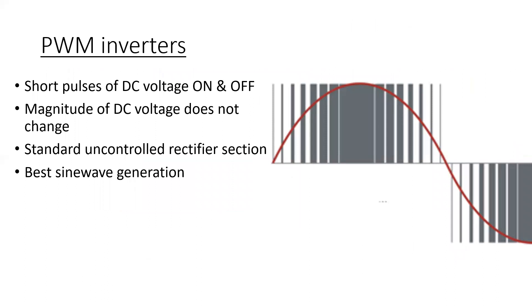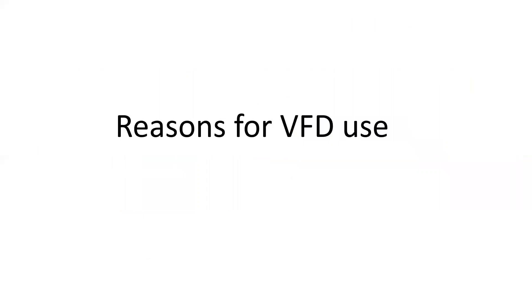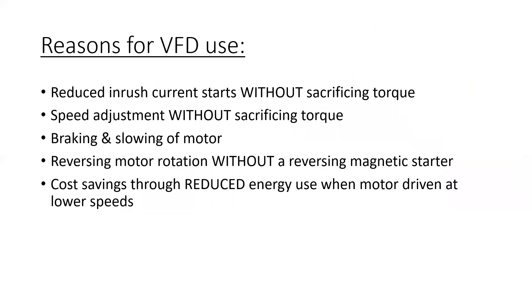PWM inverters use short pulses of DC voltage on and off. The magnitude of DC voltage does not change. It uses a standard uncontrolled rectifier section and provides the best sine wave generation. There are a number of reasons to use VFDs beyond just basic speed control: we can reduce inrush current on starting without substantially sacrificing torque, do speed adjustment without sacrificing torque, perform braking and slowing, reverse motor rotation without a reversing magnetic starter, and achieve significant cost savings from reduced energy use at lower speeds.